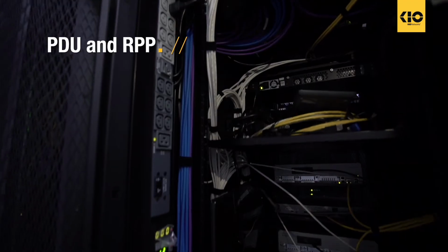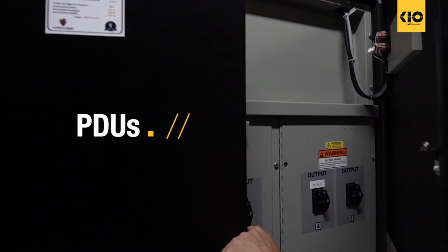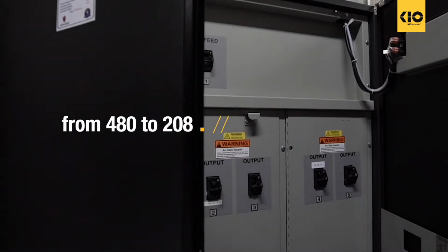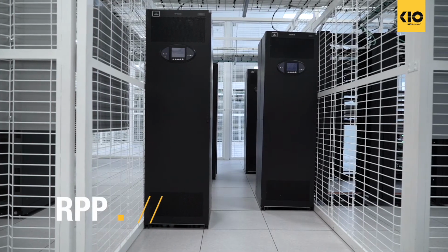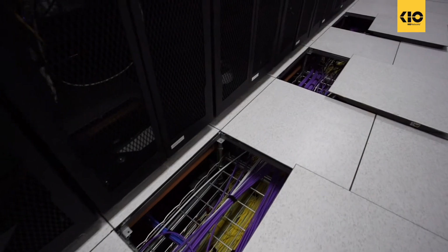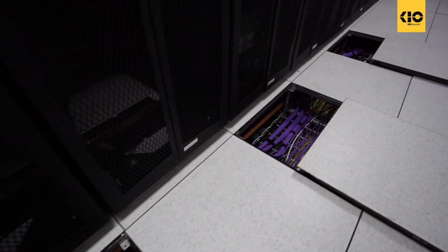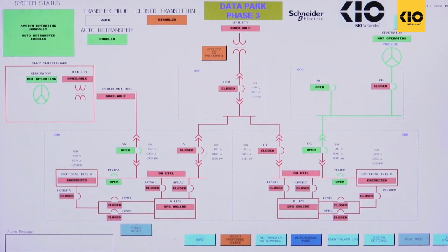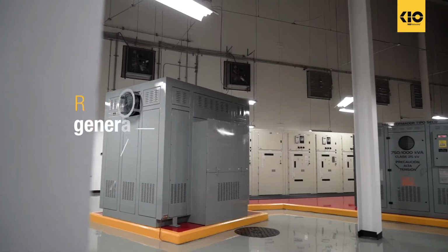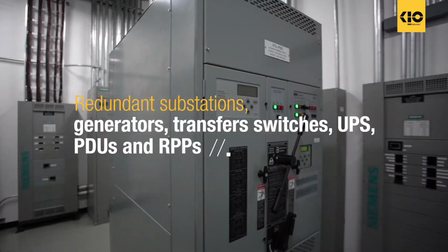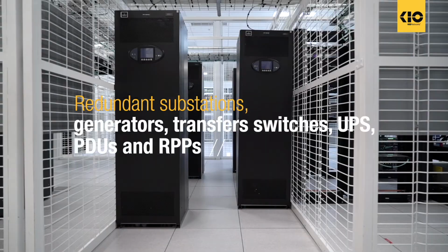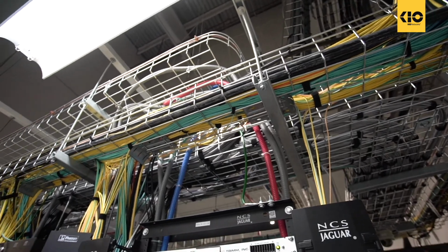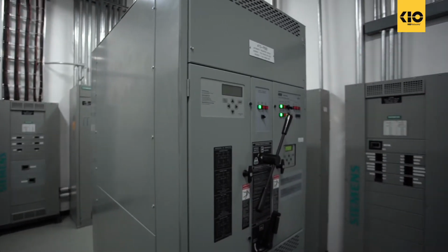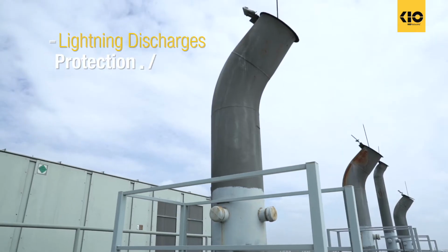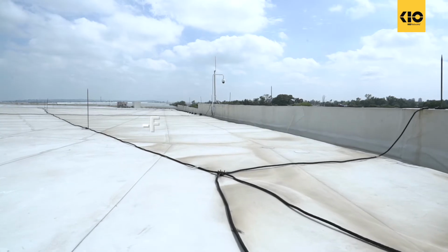Power is distributed to the racks or cabinets through PDUs to reduce the voltage from 480 to 208 volts. The PDUs are connected to the RPP distribution boards, where the power circuits provide power to the racks in a 2N topology. In summary, the electrical system that powers the IT equipment is designed with a high availability topology through 2 electrical buses with redundant substations, generators, transfer switches, UPS, PDUs, and RPPs, allowing to maintain the electrical supply in a continuous and reliable mode. For lightning discharges, we have 2 independent protection systems: Faraday cage and Franklin point.